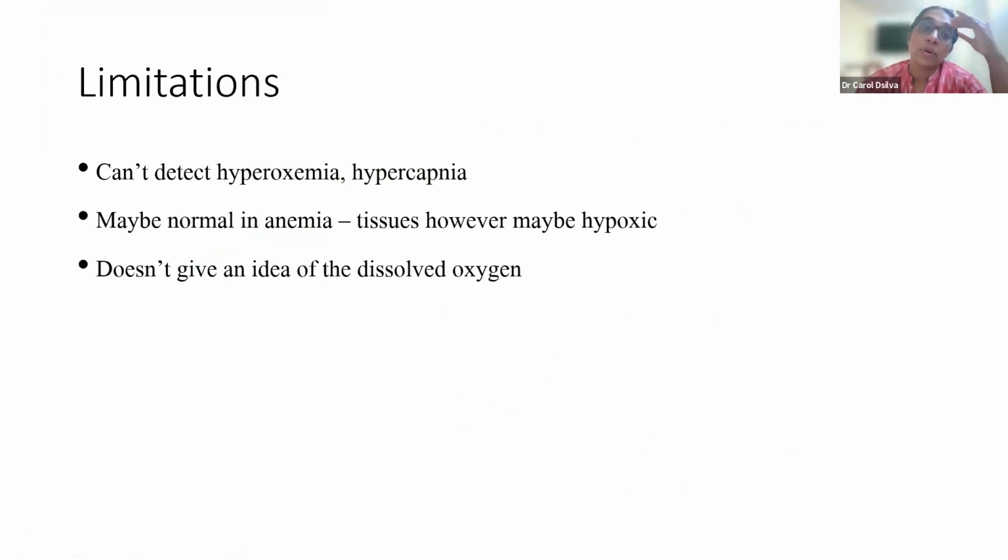It will not indicate or tell you that the patient is hyperoxic. And hyperoxemia is as bad a condition as hypoxemia. Maybe not as bad, but it is also a serious condition. It should not be ignored. Hypercapnia cannot be picked up.